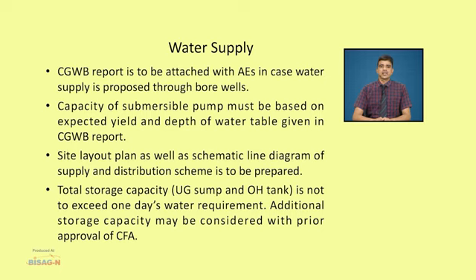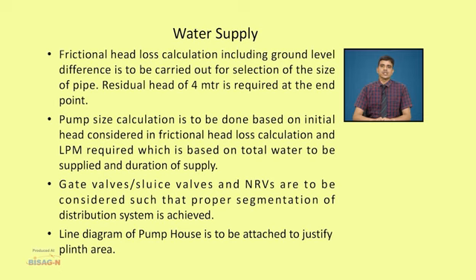Site layout plan as well as schematic line diagram of supply and distribution scheme is to be prepared. Total storage capacity, that is UG sump and overhead tank both, is not to exceed 1 day's water requirement. Additional storage capacity may be considered with prior approval of competent financial authority. Frictional head loss calculation including ground level difference is to be carried out for selection of the size of pipe. Residual head of 4 meter is required at the end point.